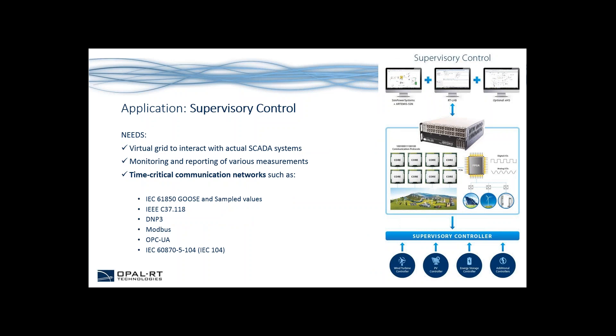The second application is supervisory control, where instead of interfacing the real-time simulation with controllers directly, we interface with a supervisory controller or SCADA system. In this case, the virtual grid is simulated and interacts with an actual SCADA system. We need to monitor and report various measurements, and use time-critical communication networks such as IEC-61850, C37.118, DNP3, Modbus, OPC, and IEC-104, all integrated for supervisory control.